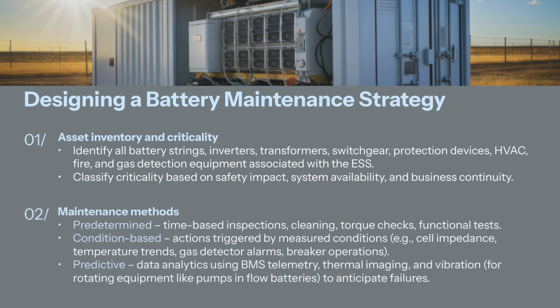Second, maintenance methods. Predetermined maintenance. This is time-based inspections, cleaning, torque checks, and functional tests. Condition-based maintenance, actions triggered by measured conditions, for example, cell impedance, temperature trends, gas detector alarms, or breaker operations. Predictive maintenance. This would include data analytics using battery management system telemetry, thermal imaging, and vibration for rotating equipment like pumps in flow batteries to anticipate failures.